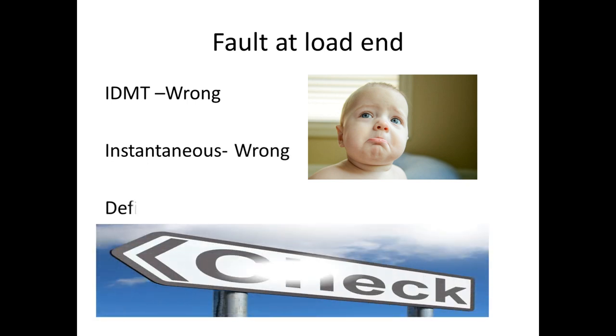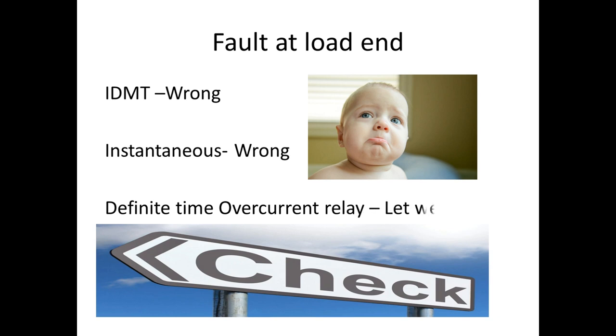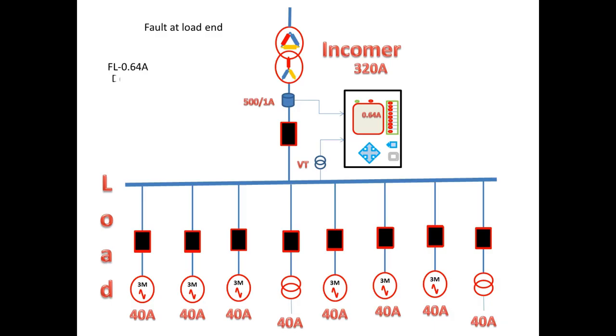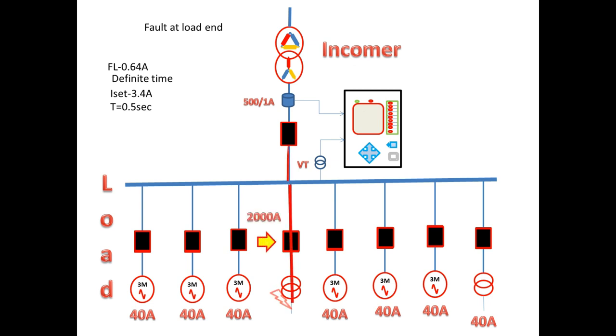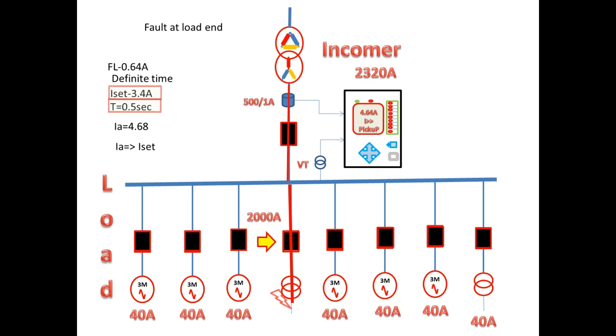When we see that IDMT and instantaneous are both not satisfactory, the third option is to select definite time. For this I am going to keep ISET equal to 3.4A and trip time is 0.5 seconds. Now the same fault occurs. Due to this fault the fault current taken is 2000A. The actual current on the secondary is 4.68A, which is greater than ISET, and the relay will pick up and start to count for 0.5 seconds.